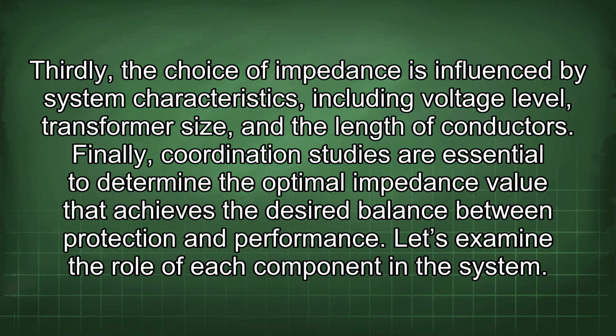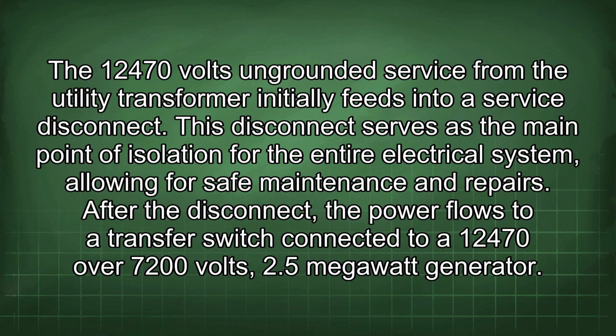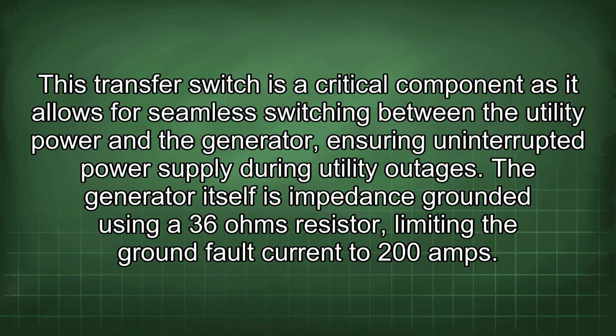Let's examine the role of each component in the system. The 12,470 volts ungrounded service from the utility transformer initially feeds into a service disconnect. This disconnect serves as the main point of isolation for the entire electrical system, allowing for safe maintenance and repairs. After the disconnect, the power flows to a transfer switch connected to a 12,470 over 7,200 volts 2.5 megawatt generator. This transfer switch is a critical component as it allows for seamless switching between the utility power and the generator, ensuring uninterrupted power supply during utility outages.